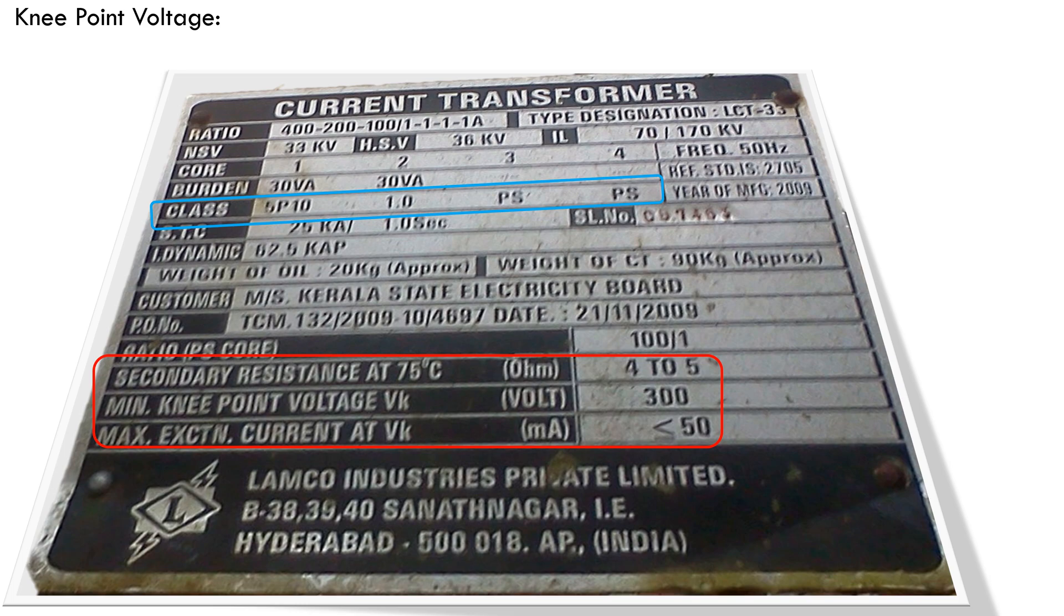Measuring core requires good accuracy up to 120%. They require low level saturation with low exciting current and knee point at low flux density. In protection cores, accuracy is not important. Require accuracy up to many times of rated current.